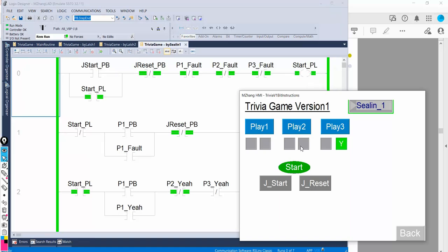You have a start button, which is J start, and then you have multiple stop buttons. So all the other conditions are just like stop buttons. The stop buttons have to be false, so right now they are green. So we use XIO. Once we press start, you can see the start, right? So that's a typical 3-wire control. It's just a variation based on the tag value.